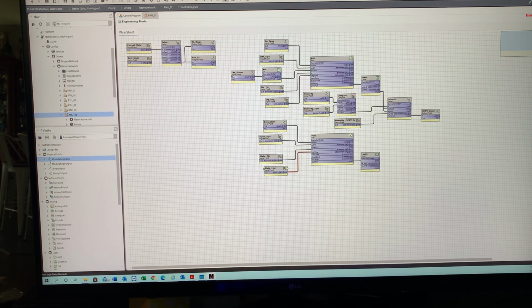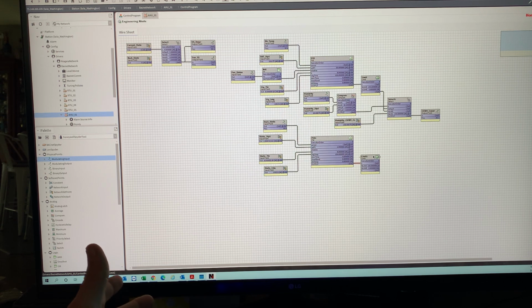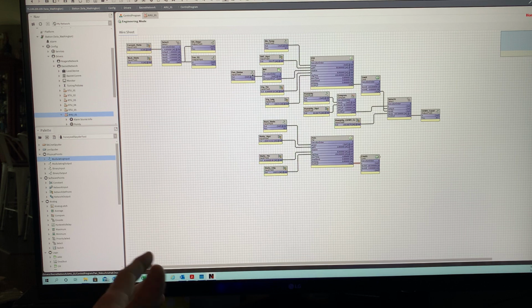the question is do we want to do a fan status? So obviously this is going to be on a VFD. We're going to modulate it. A lot of times what we do is we'll set a VFD up to, let's say, 20 hertz for minimum. So that way it's always showing some amps, and it'll allow the fan status to come into play. 15 to 20 is usually where we put our minimums. It just depends on the application. Because if you can't put 15 hertz or 15% on a VFD, and it's going to overpressurize the duct, then you got a bigger issue.